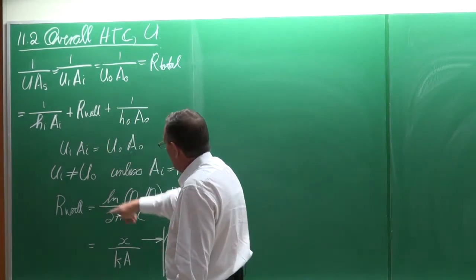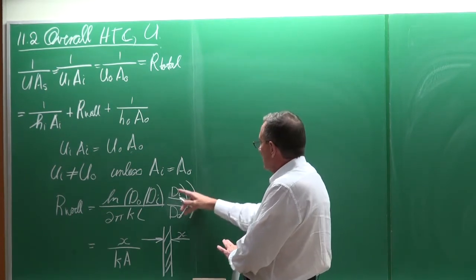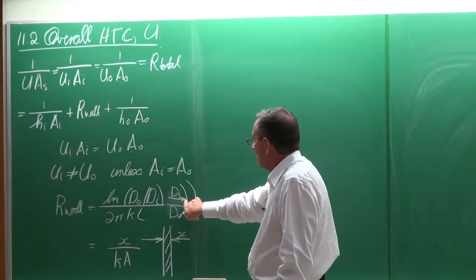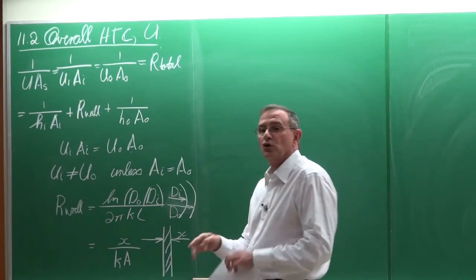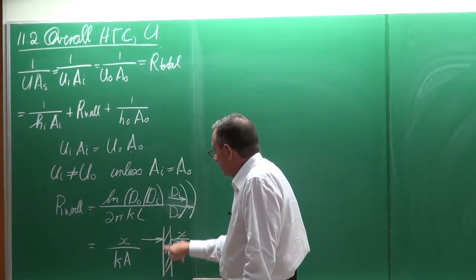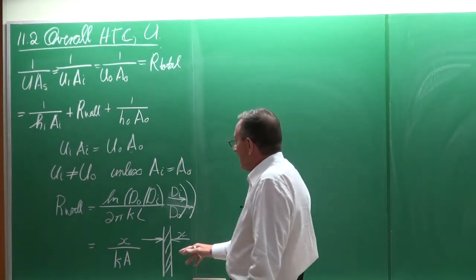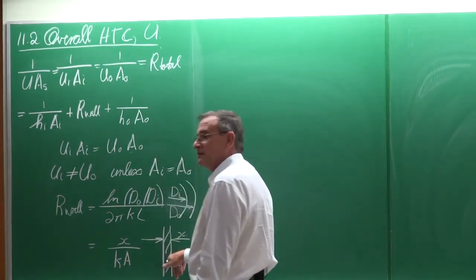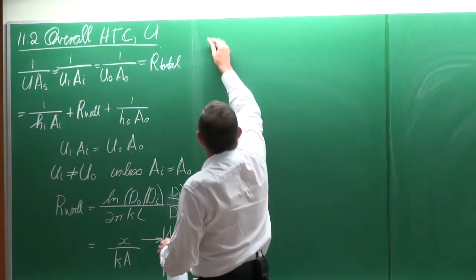In terms of the resistance of the wall, we normally look at two different types in heat exchangers. One is the tube-in-tube type, where heat transfer occurs over the wall between the inner diameter and the outer diameter. The other is a flat wall, typically found in a plate heat exchanger, where the resistance is determined by the thickness divided by the thermal conductivity of the wall multiplied by the area.